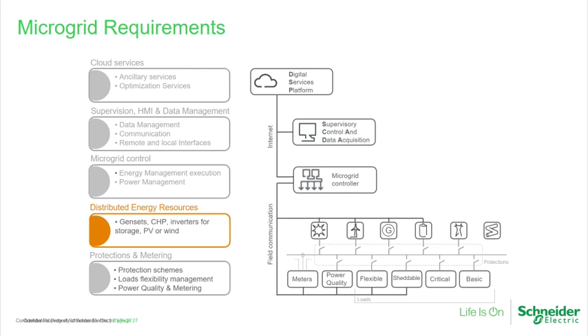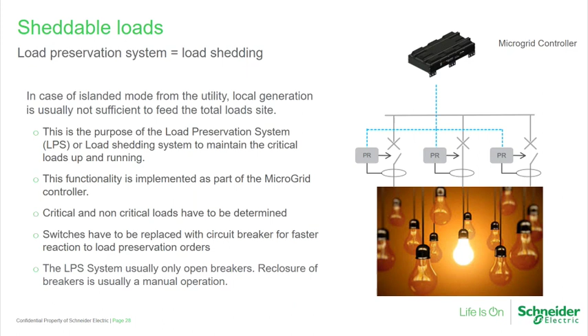Looking in a bit more detail about some of the asset controls, one of the very simple things, I'm sure Rupert would say too, in the early days of microgrids was very simple load shedding to maintain your frequency. It's still doing that now, but on a more automated basis. Obviously, what you need to make sure is your critical and non-critical loads have been determined.